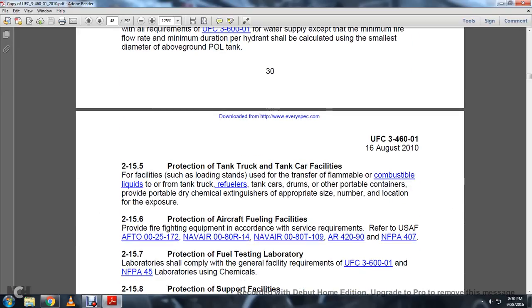215.5 Protection of Tank Truck and Tank Car Facilities. For facilities such as loading stands used to transfer flammable or combustible liquids to or from tanker trucks, fuelers, tank cars, drums, or other portable containers, provide a portable dry chemical extinguisher of appropriate size, number, and location for the exposure.